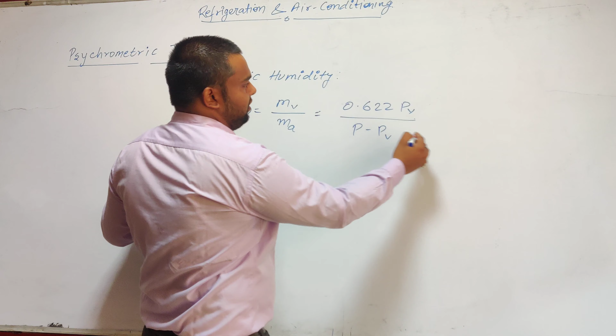First one is specific humidity. It is denoted by omega. Specific humidity may be defined as the ratio of the mass of water vapor to the mass of dry air at the same temperature and in the same volume. It can be expressed as 0.622 Pv upon (P minus Pv). The unit is kg per kg of dry air. This kg comes from kg of water vapor, and this is per kg of dry air.